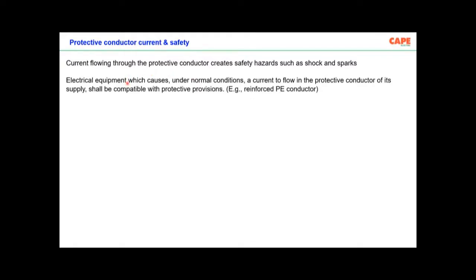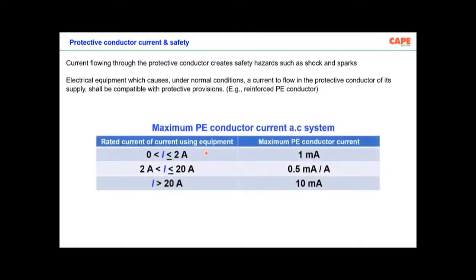Now, the maximum amount of PE conductor current in an AC system is, you can see here, for a line current of up to 2 amperes, the maximum leakage current expected in a protective conductor, that means an earth conductor or a green and yellow wire, is 1 milliampere. For load more than 20 amps, the maximum current expected in your protective conductor is 10 milliampere. This is for one condition. There are probably some more conditions which I am not explaining, but basically what you should understand is that the continuous current flow through the earth wire must be negligible, very, very small.